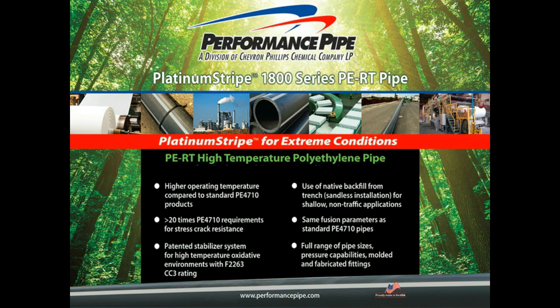The first one is wanting to know, are there current applications that require the new PERT materials rather than the standard polyethylene materials? The answer to that one is essentially that the hottest temperature standard PE4710 can withstand continuously is 140 degrees Fahrenheit. So any applications that are above 140 is where the PlatinumStripe would come into play, up to roughly 180 degrees Fahrenheit.